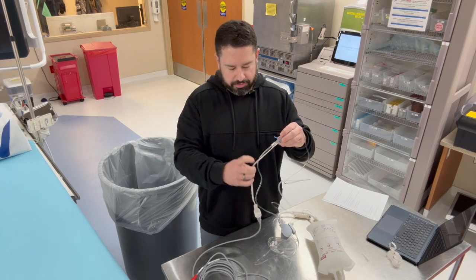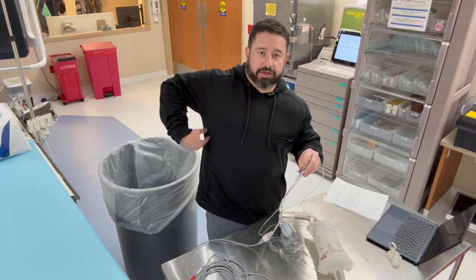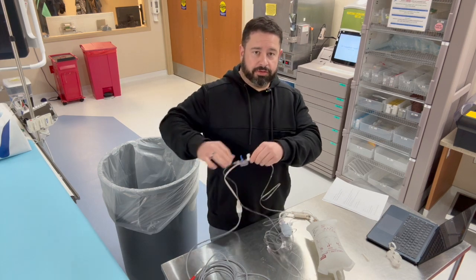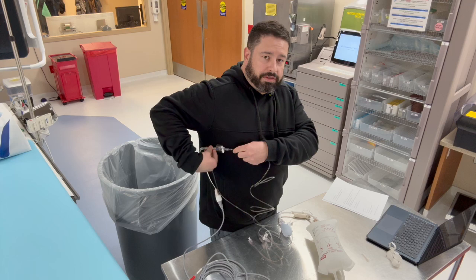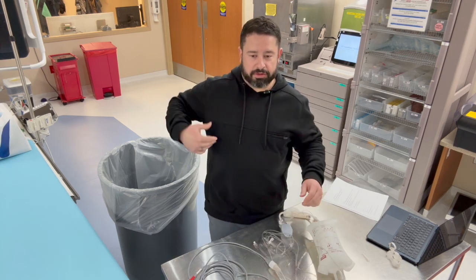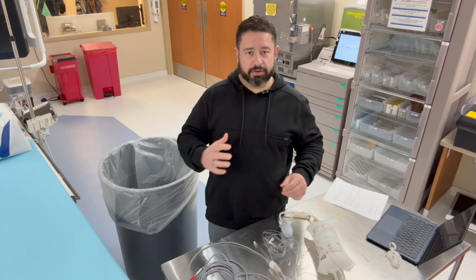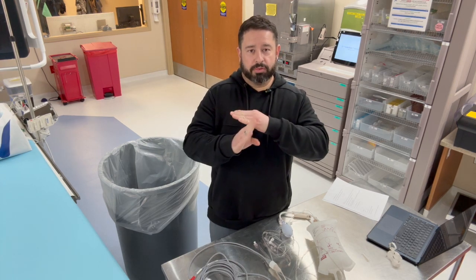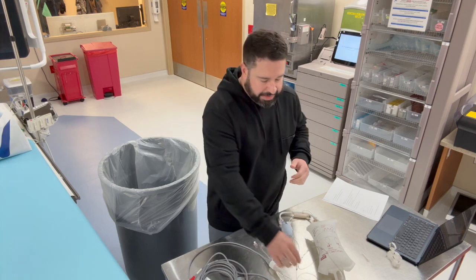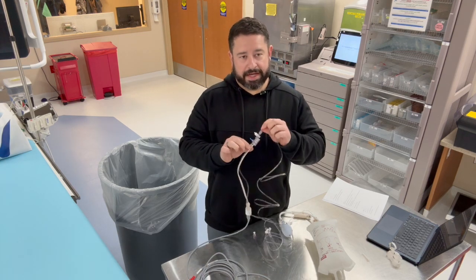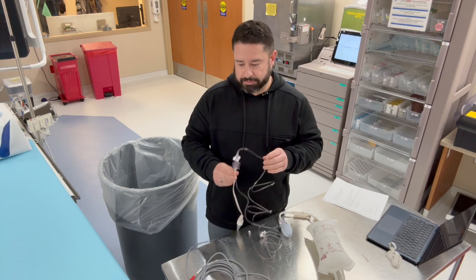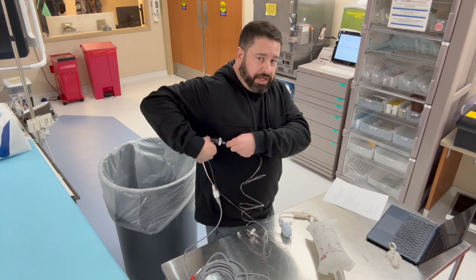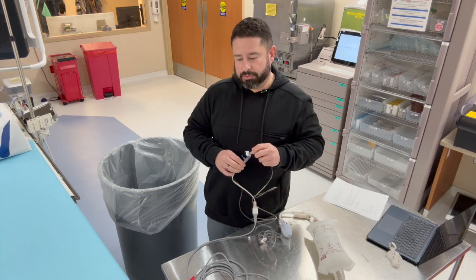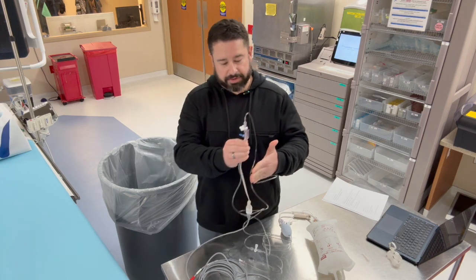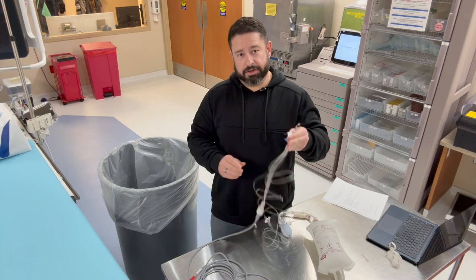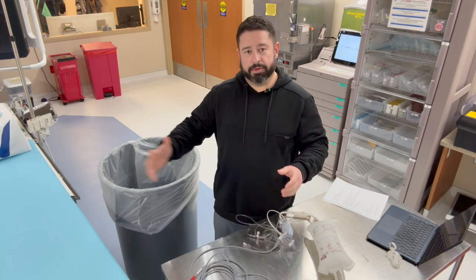First, you need to get this to the right point. In transport, it's very easy just to take this transducer and tape it to the side of the patient. There's a point here at the fourth intercostal space, mid-axillary line that we call the phlebostatic axis. It is a crossing point here at the level of the heart, and that is where you get the most accurate reading, and that is where the transducer should stay. So in transport, again, you can tape it to the patient if you need to, or if you have a clip, they make clips that this transducer slides into, and then you can take your clip and clip it to an IV pole, maybe on the end of your stretcher.